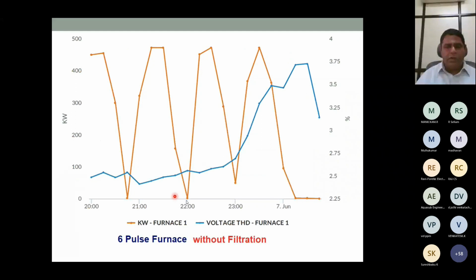One of the examples with voltage harmonics, I would like to show to everyone of you. It's with a 6 pulse furnace without any filtration. The brown color is the load variation in the furnace. It was switched on here and at full load, it was switched off. Again, the furnace went on, again came down. According to the load variations, there is no variation in the waveform of the voltage harmonic. This is independent of the load. So voltage harmonics is not dependent on the load. This is what this graph is trying to tell us.